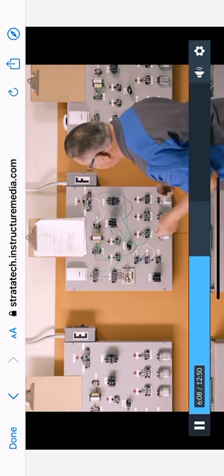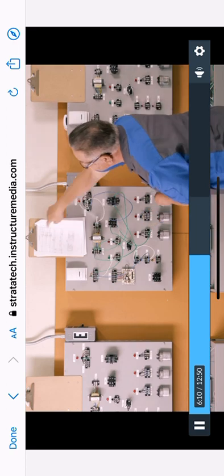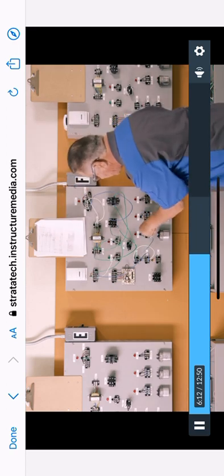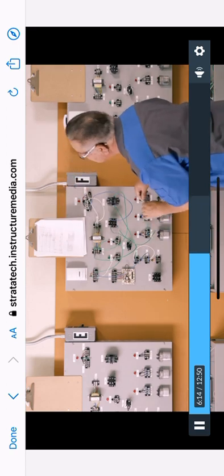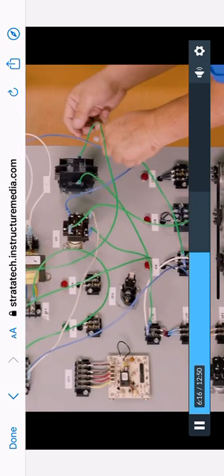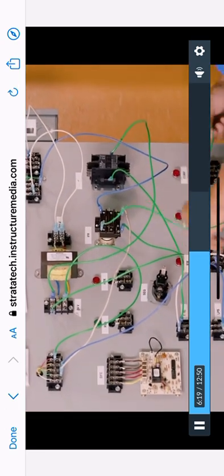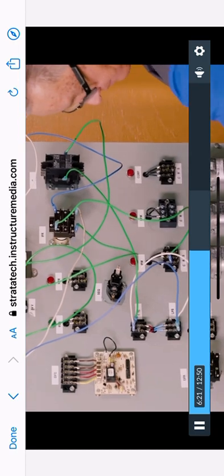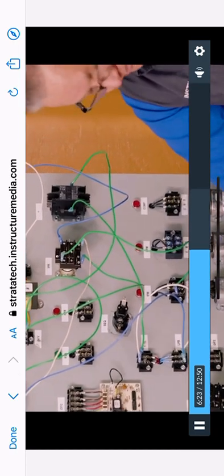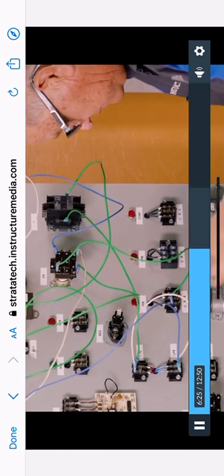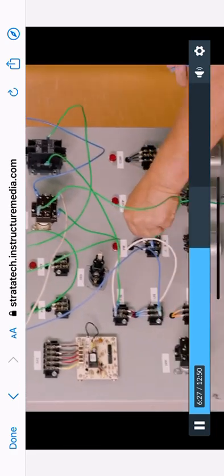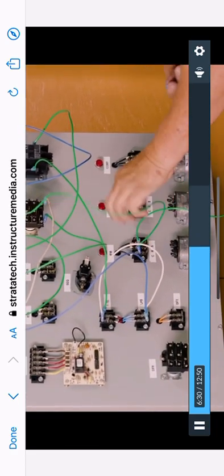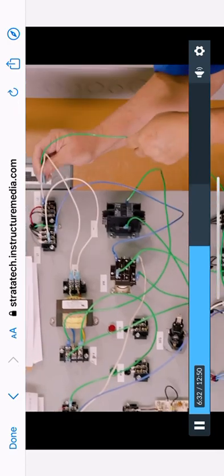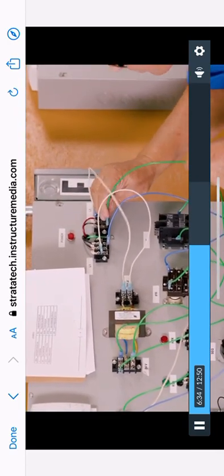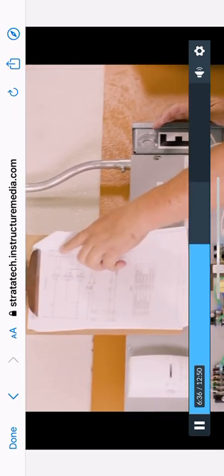So I'm going to get a wire on my run winding right there on the motor, the R terminal, and I'm going to go straight to my line 2, which is up there, which I need a longer wire. Here it goes. So my run is going to go from here on the motor to my line 2, which is that wire there I just put on.